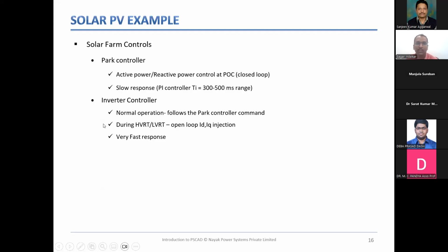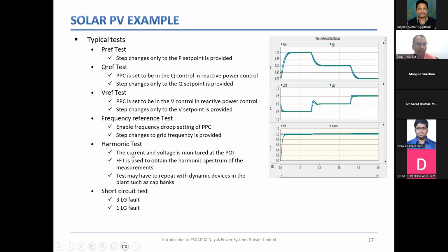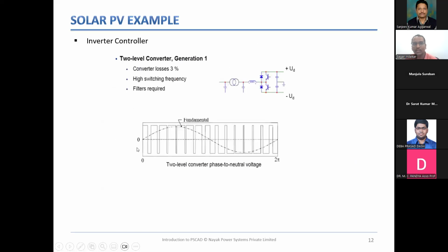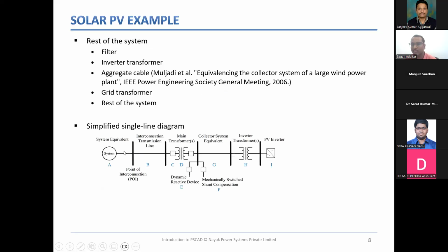Then you have your inverter control, which follows the PPC and operates during LVRT, HVRT. It takes a decision, and it's a very fast controller because it is part of the power circuit. Now, once you model all these things, you model grid, you model your transmission line, you model your transformers, collector system, filters, any reactive power compensation devices, your inverter and your converters and your PPC. Once you put all these things together, you have to perform a study.